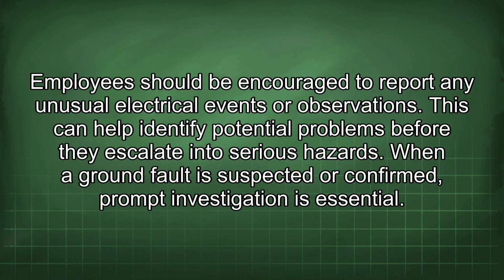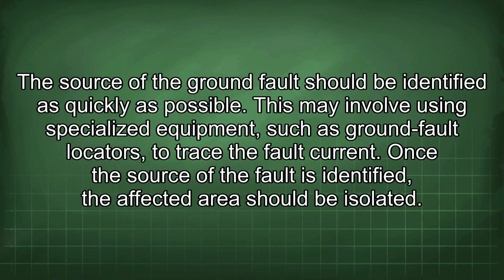Employees should be encouraged to report any unusual electrical events or observations. This can help identify potential problems before they escalate into serious hazards. When a ground fault is suspected or confirmed, prompt investigation is essential. The source of the ground fault should be identified as quickly as possible.